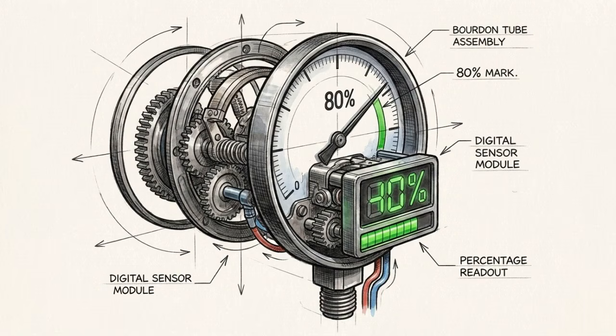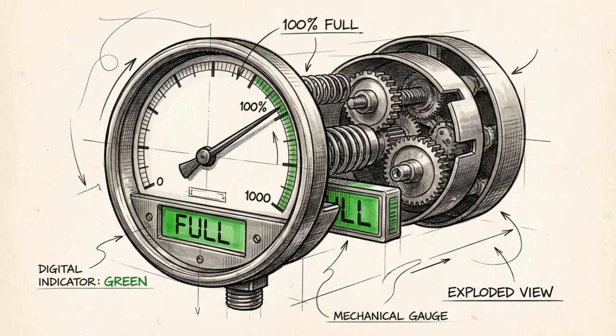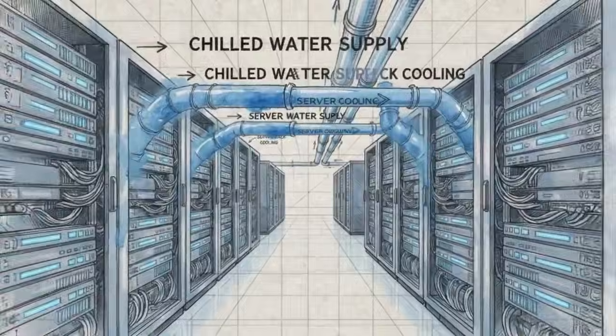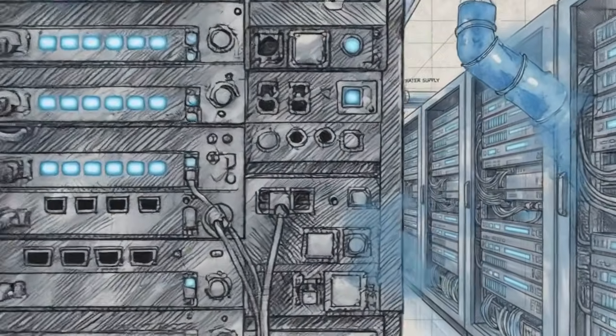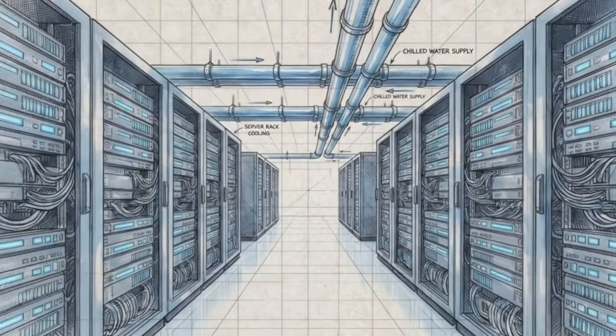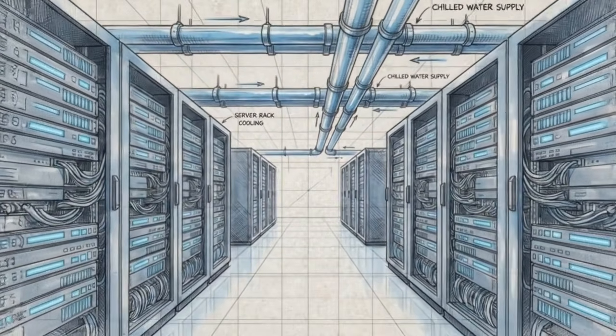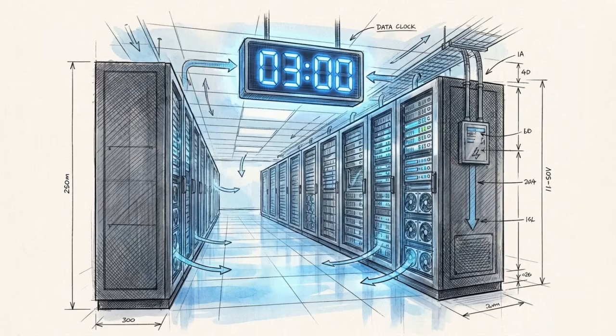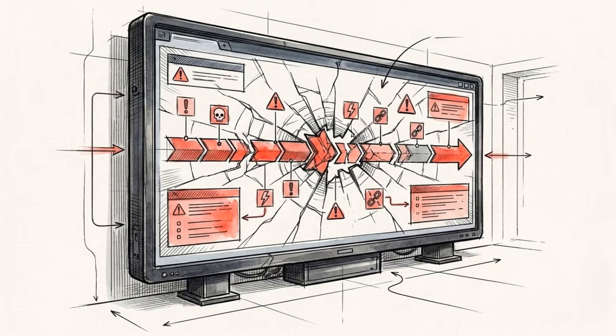The mechanical train must reach 80% capacity stability at 75 seconds and achieve 100% of the required plant capacity by the 180-second mark. Surviving that 3-minute window is an exact orchestration of fluid physics, precision electrical switching, and carefully calculated thermal buffering. When all systems function perfectly, the plant recovers in under 3 minutes. But data center engineering requires planning for the moments when the timeline breaks and automated recovery sequences fail.